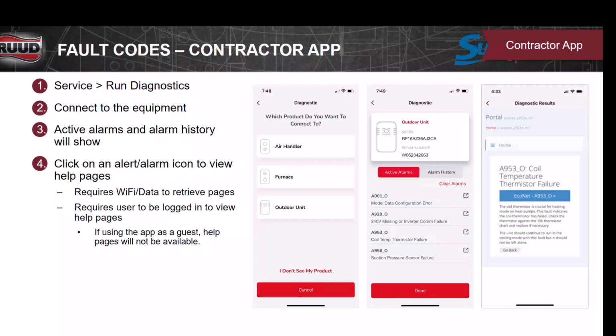So this one is locked out on several error codes, one of them being A953_O. Now that _O is important because that's telling me it's an outdoor unit. If it was in the air handler, it'd be _A. So I know now I'm having a problem with the thermistor.